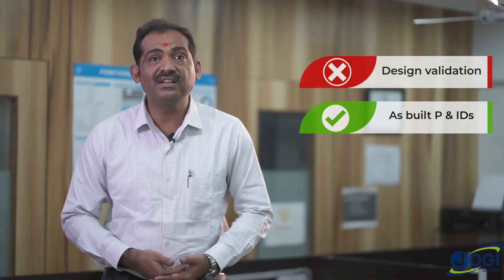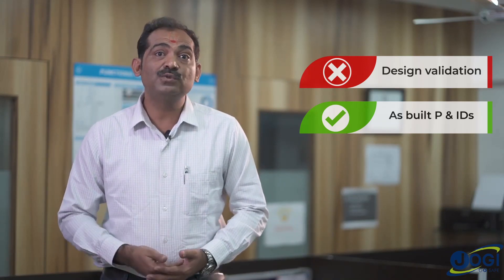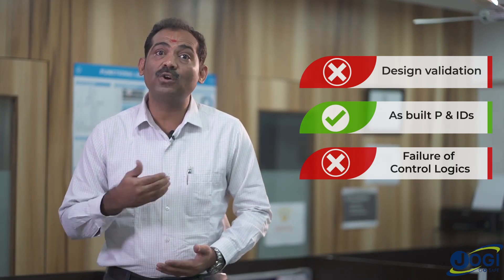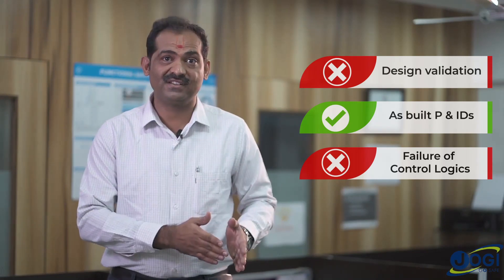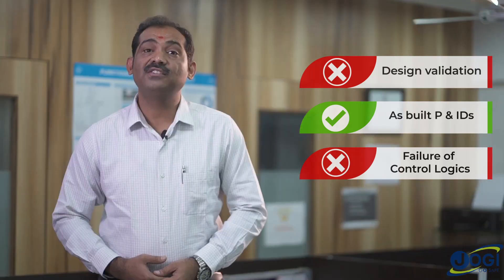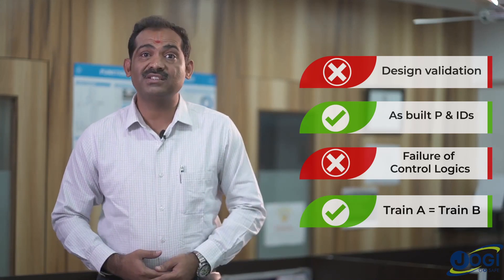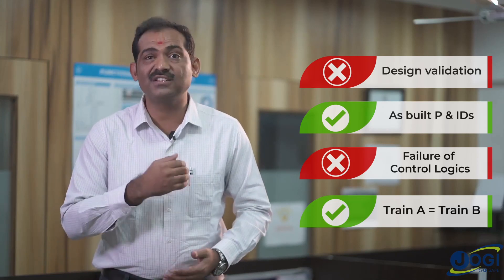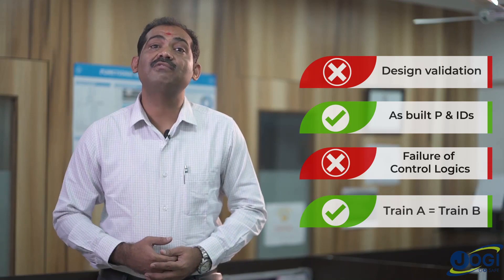Third, when identifying causes of process deviations, we should not consider the failure of control logics or control systems as a cause. Fourth, when there are two or more similar systems or trains, conducting HAZOP for one system need not be repeated for the remaining identical systems.